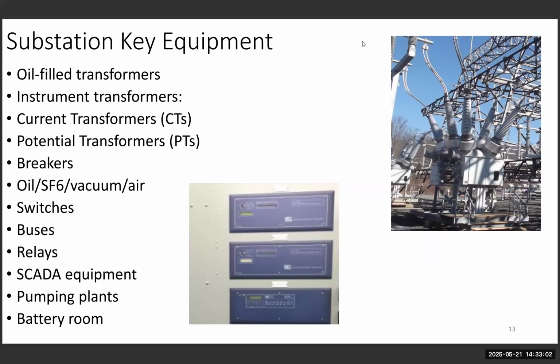Okay, excellent, Roger. So basically, you kind of hit it, we have to monitor the temperature. If the transformer gets extremely hot, whether from something loose, something damaged, or just because of overload, it's going to be a problem. And you are right, 100%. And basically, the answer really is it's an oil-filled equipment. That means it produces the most risk, and it has thousands of gallons of oil.